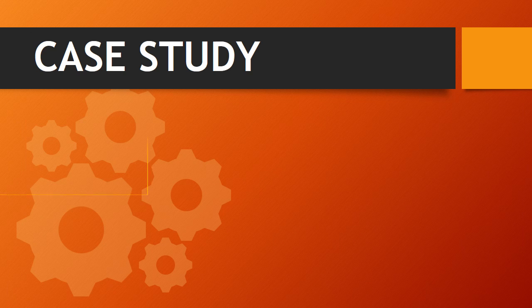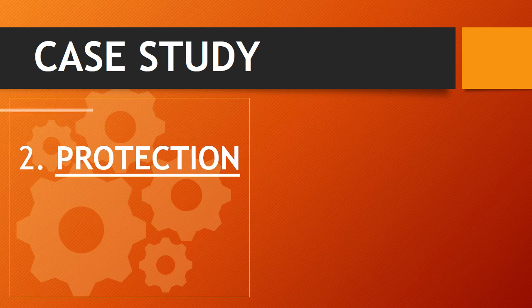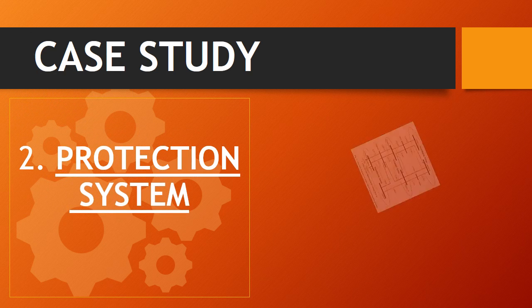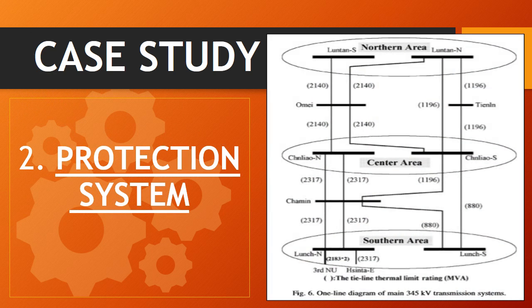In case study, the next section is the protective system. Figure 6 is on the screen. This figure depicts a one-line diagram of the main 345 kilovolt transmission system connecting the north, the center and the south areas. The surplus power in the central and southern areas is transmitted to the north through 2 parallel circuits. Every circuit has 2 parallel 3-phase transmission lines which are built on the same iron tower.